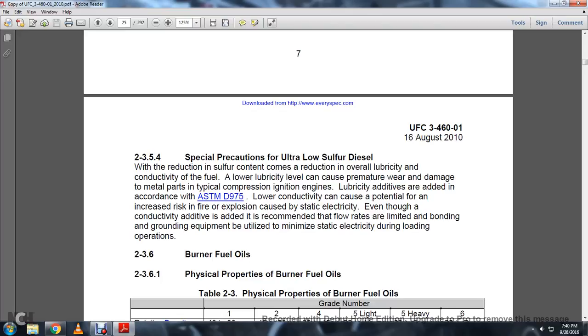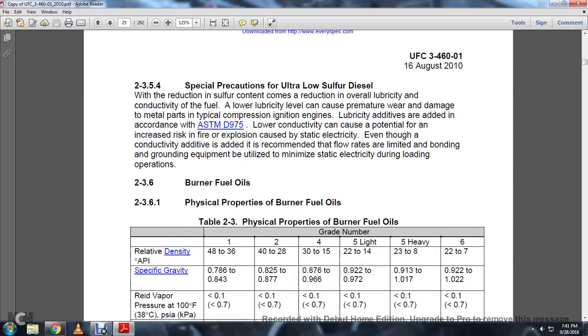2.3.5.4 Special precautions for ultra low sulfur diesel. With the reduction of sulfur content comes a reduction of overall lubricity. Low lubricity of the fuel can cause premature wear and damage to metal parts. In typical compression ignition engines, lubricity additives are added in accordance with ASTM D975. Lower conductivity can increase the risk of fire or explosion caused by static electricity, even though conductivity additive is added. Recommended flow rates are limited, and bonding and grounding equipment is utilized to minimize static electricity during loading operations.